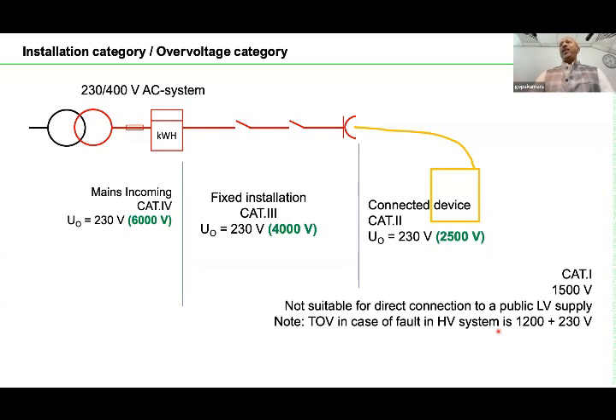Okay, utility. The power supply which is coming from the utility. Actually, the class 1 device we are not supposed to connect directly to the utility transformer. We are not supposed to, because it will fail. In case of any fault on the HT side of the transformer, the LT side of the installation can experience a temporary overvoltage and these devices will not withstand it. That is the reason.